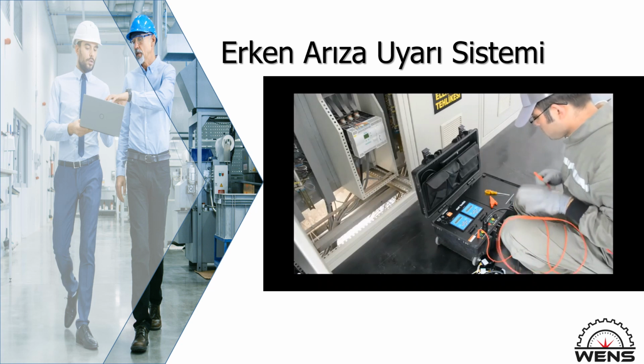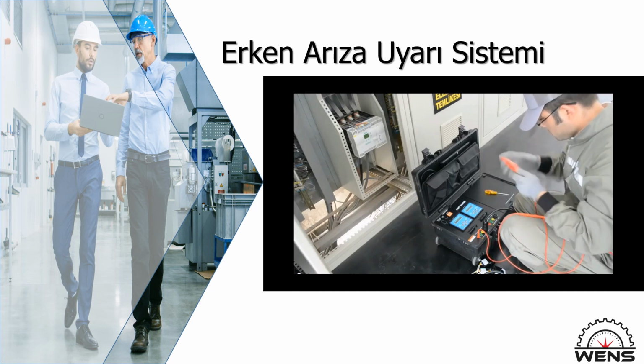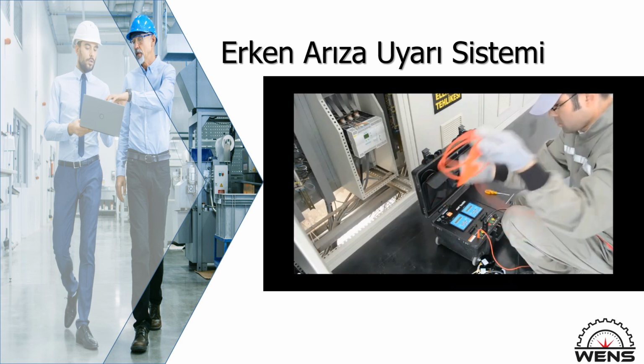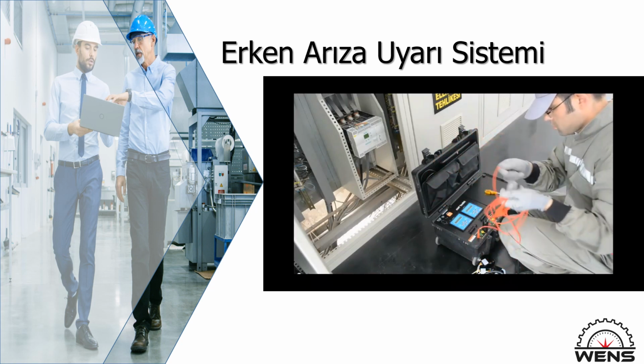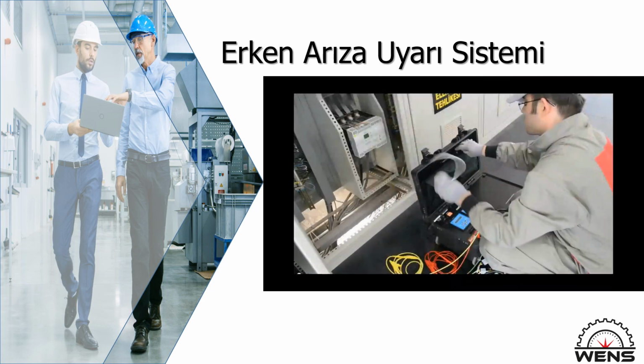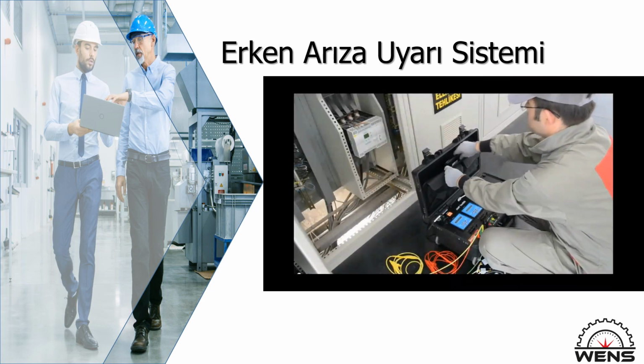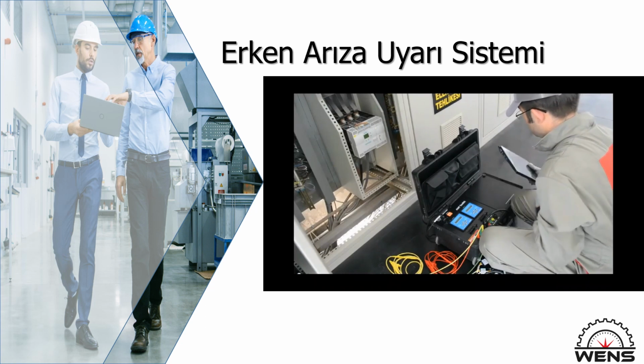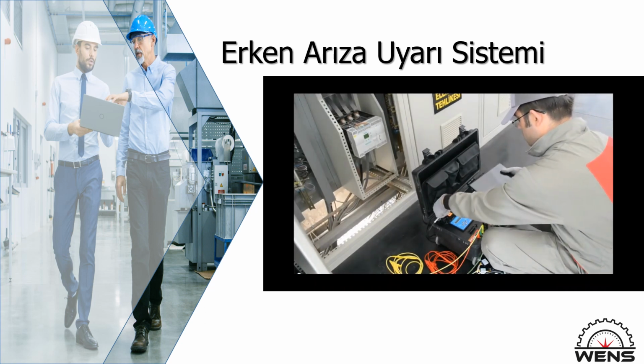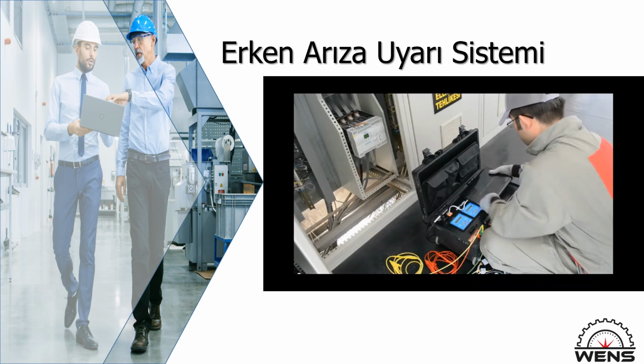AMT Toolkit includes 2 asset management units with different current levels, so it allows to use both 1 ampere and 5 ampere current transformers, which are already installed into MCC cabinet. To get voltage connection, 3 insulated alligator clips are included in the AMT. Artisys AMT Toolkit is connected to motor cables using current sensors and voltage cables.